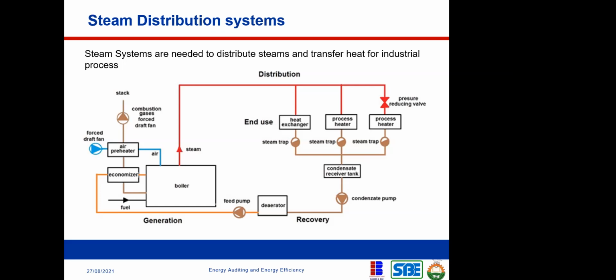And it's also a poor quality heat. Heat in the form of hot water is a poor quality heat compared to heat in the form of steam. So we want to get rid of that poor quality heat, which is now in the form of water. That is why it is important to remove steam that has returned back to water, and we call them condensates. If you look here, you're going to see what we call the condensate receiver tank. When you recover this condensate, you're not going to throw away this water because it's very pure. It does not have impurities.